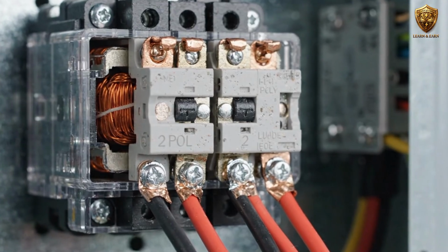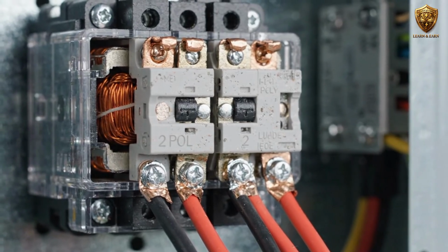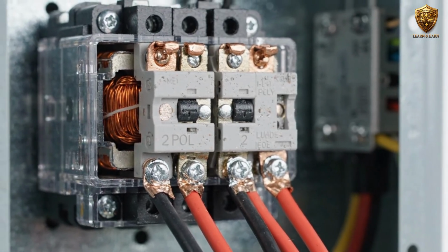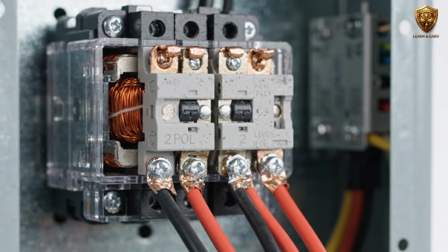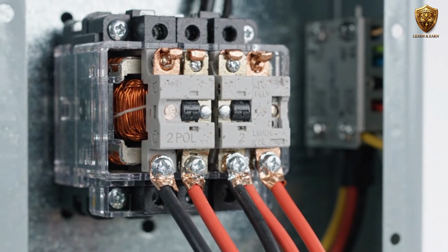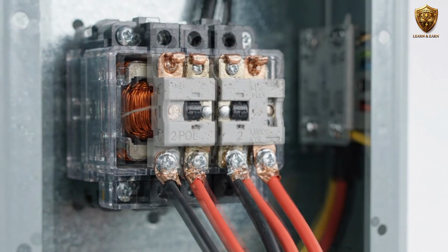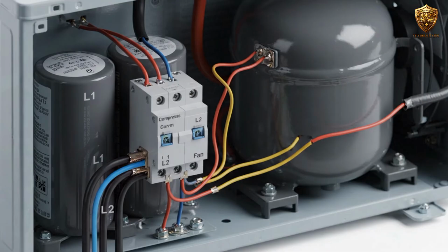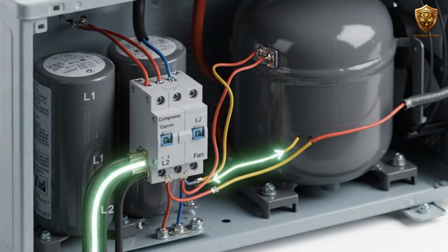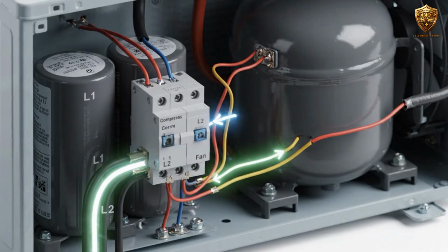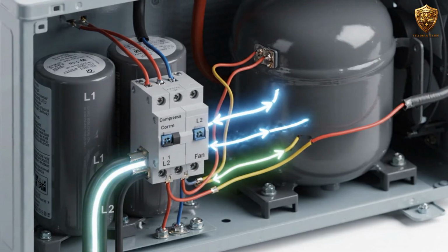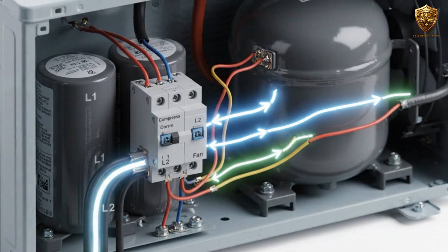The contactor also needs careful inspection. Burned or badly pitted contacts can create excessive resistance and voltage drop. But again, a damaged-looking contactor is not the only possible fault. The technician should understand what voltage should be present at each point before deciding what has failed. This is why an electrical schematic is one of the most useful tools in HVAC troubleshooting.